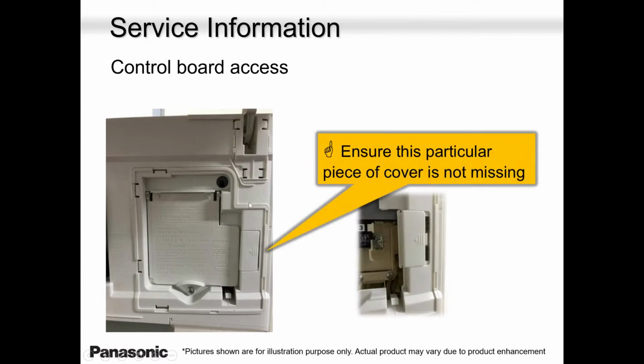so on our indoor unit, if you need to measure any voltages, open up this cover here. You will see number 1, number 2, number 3 and ground that came from the outside unit. Okay, that came from the outside unit. Measure the voltages. If you're getting fluctuating voltage, if you're not getting fluctuating voltage, check. Sometimes when the technician is using the remote controller, they cannot hear the beep.